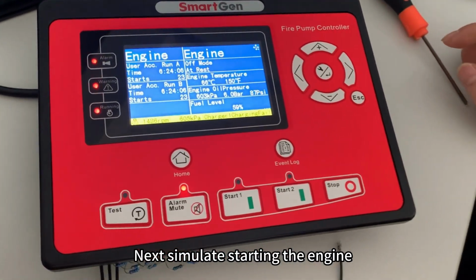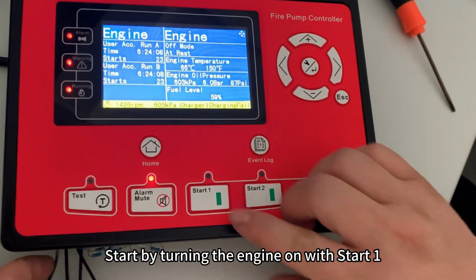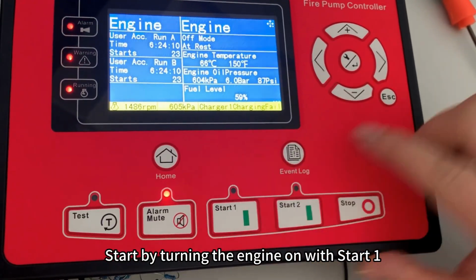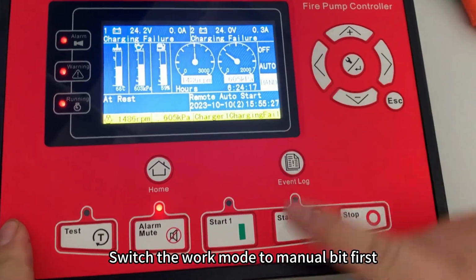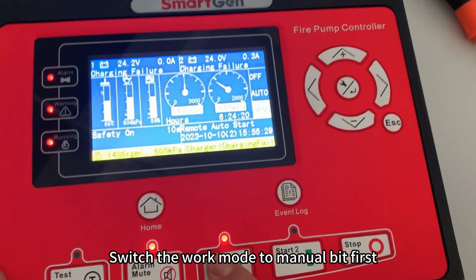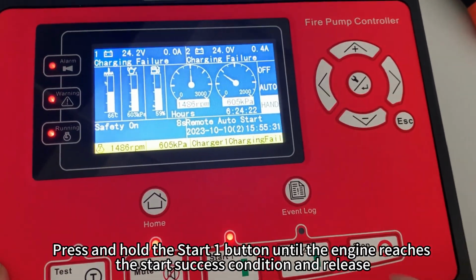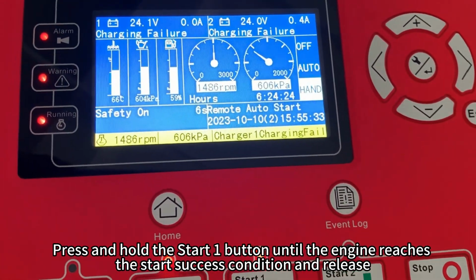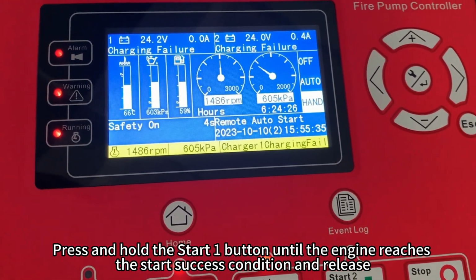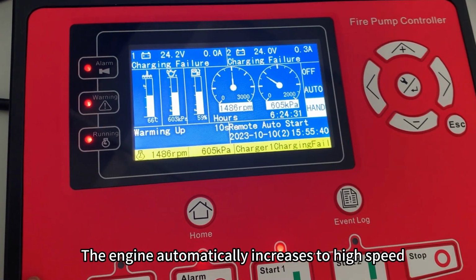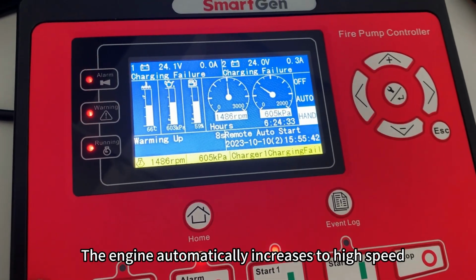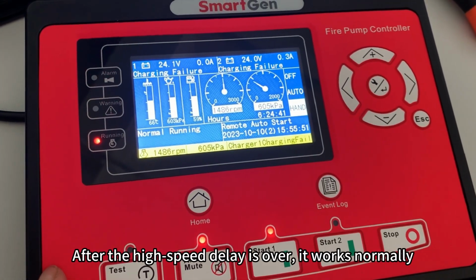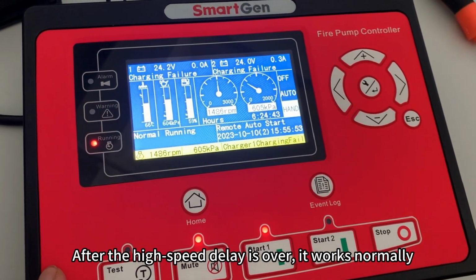Next, simulate starting the engine. Start the engine with start 1. Switch the work mode to manual first. Press and hold the start 1 button until the engine reaches the start success condition, then release. The engine automatically increases to high speed. After the high speed delay is over, it works normally.